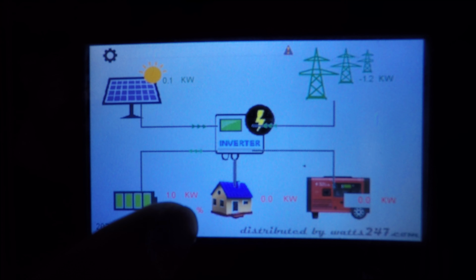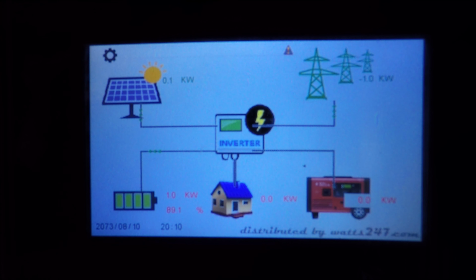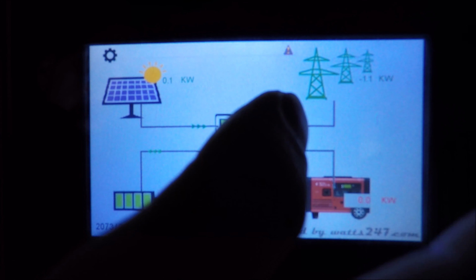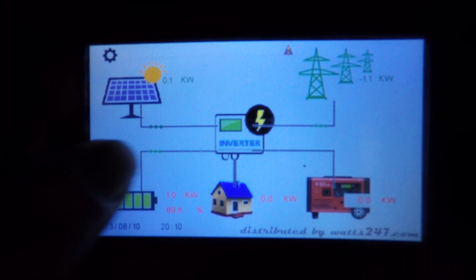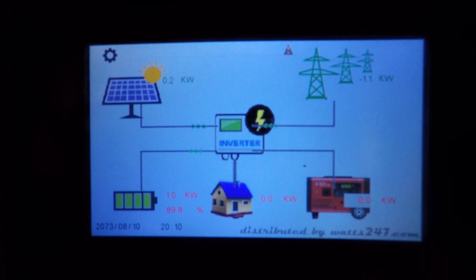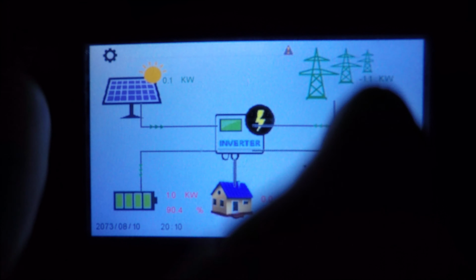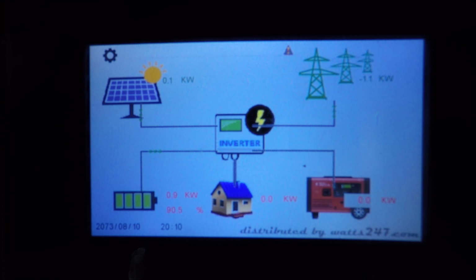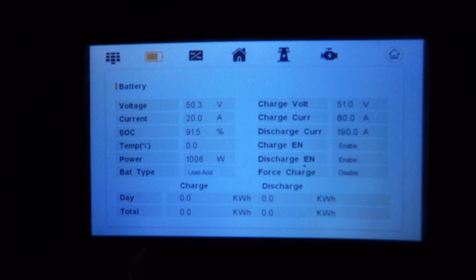So we have 1 kilowatt going into the battery, and you can see it's pulling power in from the grid, it's pulling power in from the solar, and it's pushing it into the battery. If you were doing a grid feed setup and you were feeding back to the grid, you would be able to see the directional arrows going into the grid if you were sending positive electricity back into the grid. Now we'll go into our battery settings, and we can see now we're charging at 20 amps and increasing the state of charge of our battery.